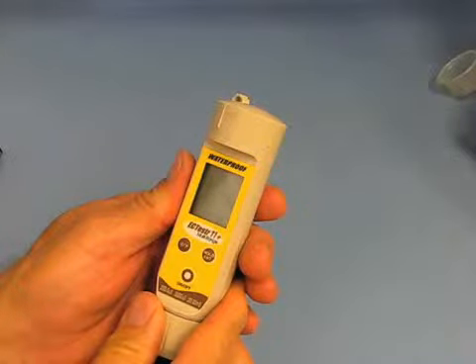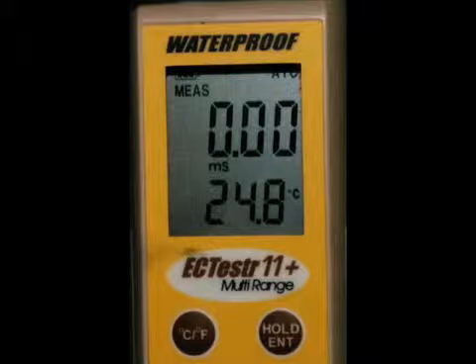When you turn the meter on by pressing the on-off button, 3 diagnostic screens are displayed in rapid succession. Ignore these displays for now unless you have a problem with your meter. The standard display includes a battery life indicator in the upper left corner, ATC, automatic temperature control, in the upper right corner, and the abbreviation MEAS indicating that the meter is in measurement mode on the left side above the larger electrical conductivity or EC value. Below the larger numbers should be a small indicator, a small m and a capital S indicating millisiemens. If a microsiemens symbol is displaying, that's a small u with a capital S, you need to change some of the meter settings as described later in this video. Temperature is displayed at the bottom of the display in either Fahrenheit or centigrade.